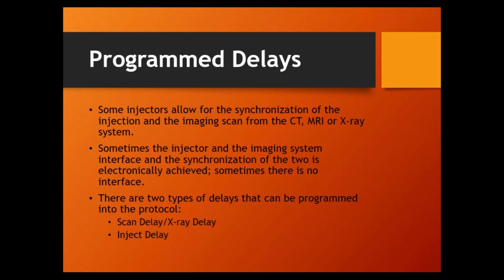Most of the time, they don't want to start both the imaging system and the contrast injector at the same time. I want to do one, I want to get one going, then fire the other one. Right? Now, if I want the imaging system to start doing its thing first, and so many seconds later, the injector started injecting, I need to program in an inject delay. 1 or 2 seconds, something like that.